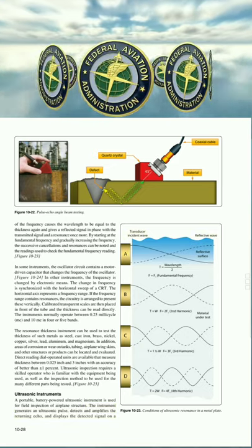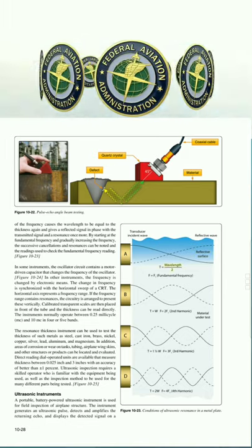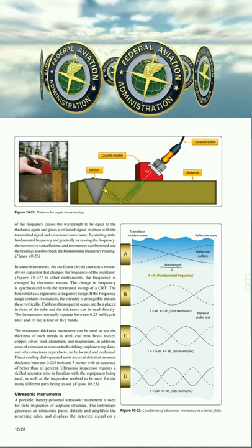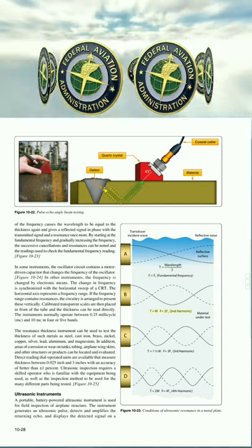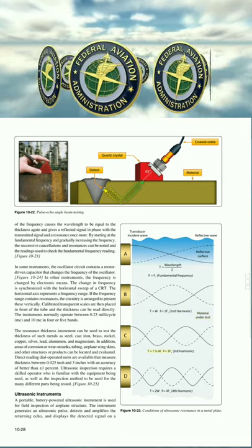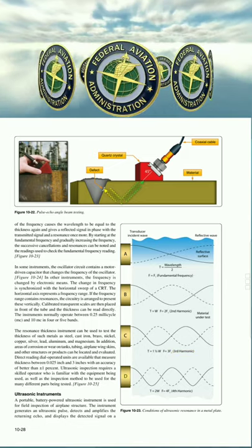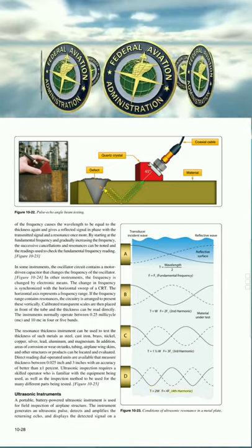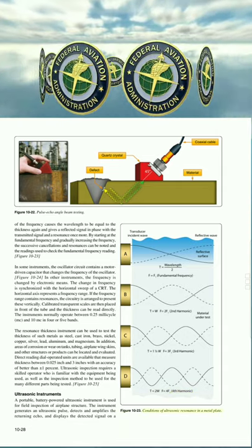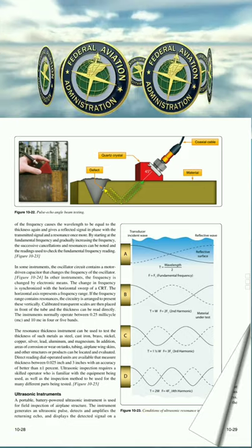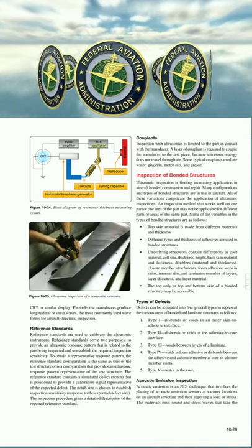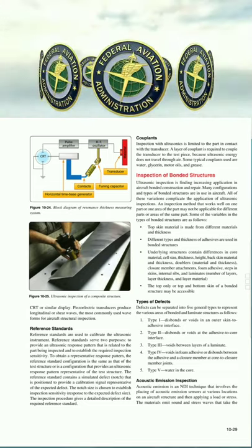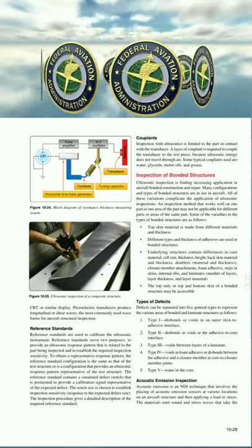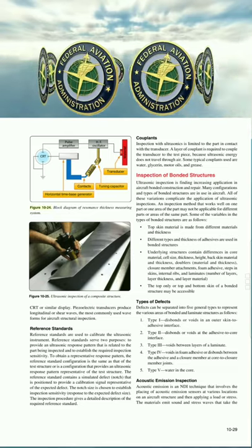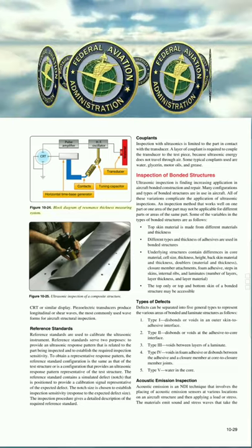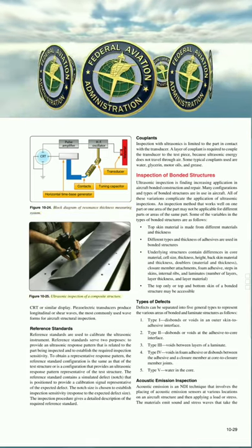Transducer, incident wave, reflective wave, a reflective surface. T equals wavelength over 2, F equals F1, fundamental frequency. B, T equals wavelength, F equals 2F1, second harmonic, material under test. C, T equals 1 and 1/2 wavelengths, F equals 3F1, third harmonic. D, T equals 2 wavelengths, F equals 4F1, fourth harmonic. Figure 10-23. Conditions of ultrasonic resonance in a metal plate. Pulse amplifier, H.F. oscillator, CRT, material, motor, transducer, contacts, tuning capacitor, horizontal time base generator. Figure 10-24. Block diagram of resonance thickness measuring system. Figure 10-25. Ultrasonic inspection of a composite structure.